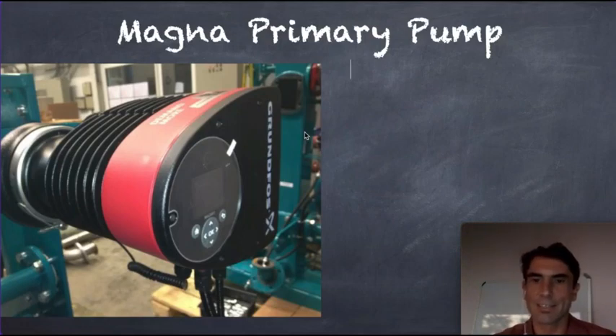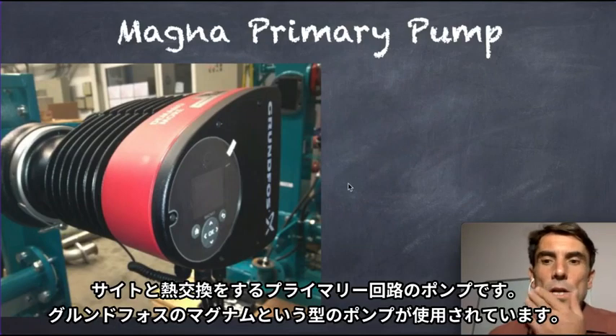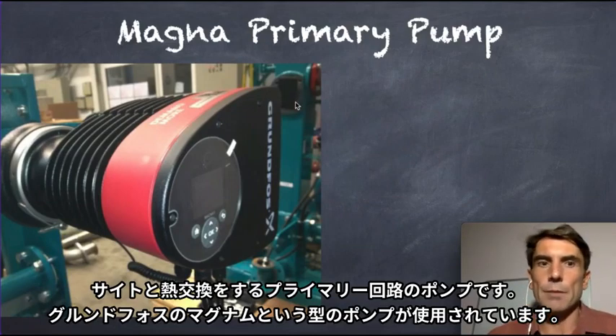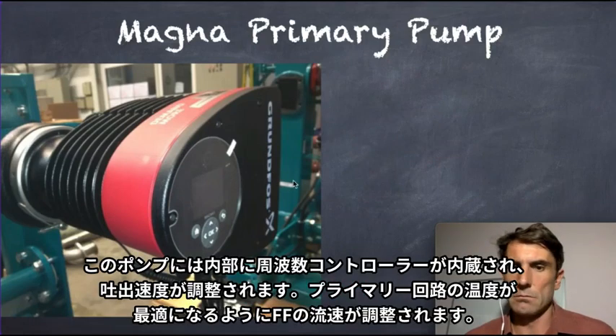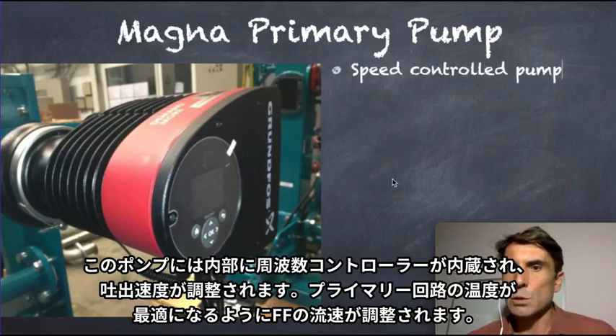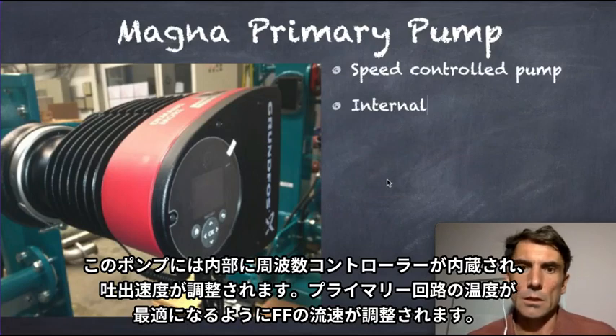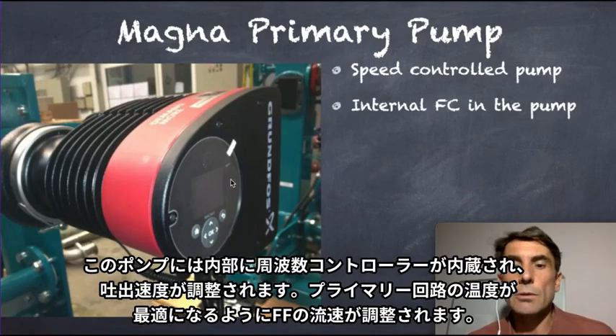One second. So, okay. Here is the primary pump. It's a Grundfos Magna pump. This pump is speed controlled. So that pump has an internal frequency converter.